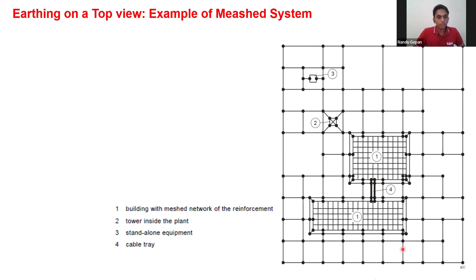A lower earth impedance will result in lower lightning currents entering the installation. If you have a very proper meshed system, I think the mesh spelling is wrong, then the lightning which is entering the structure will also be reduced to a very small value.